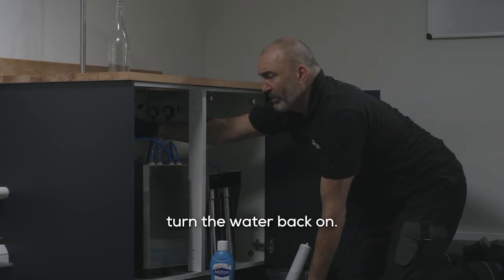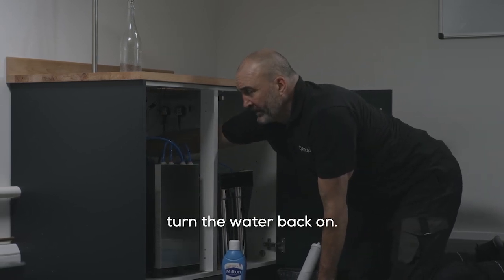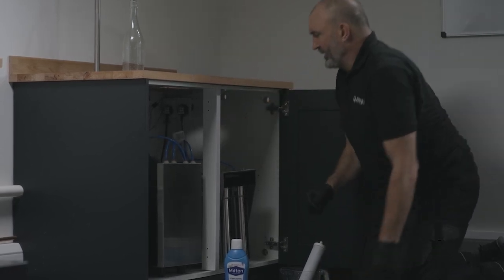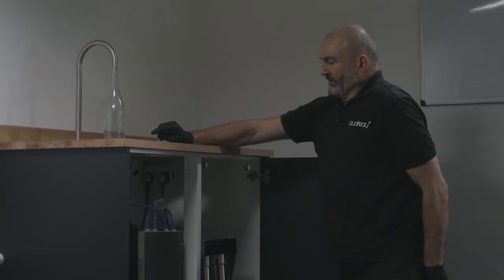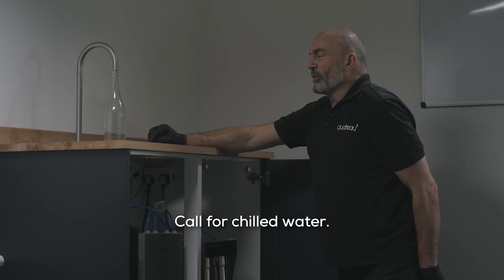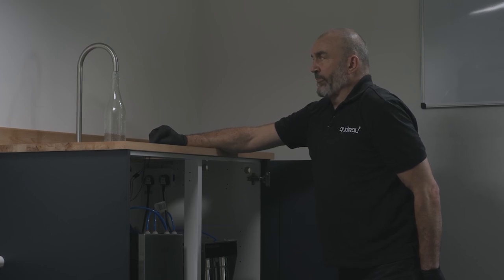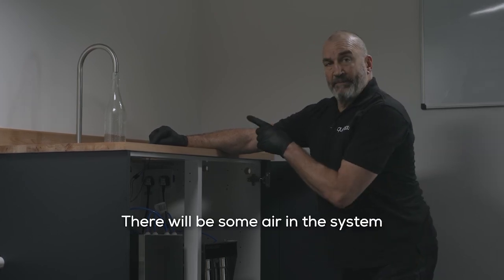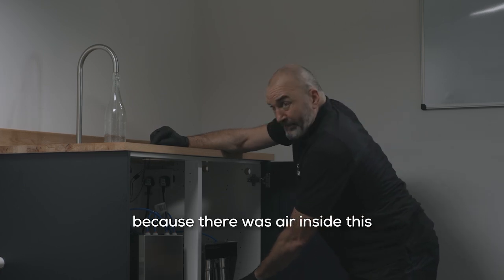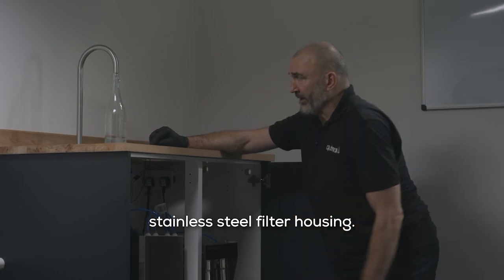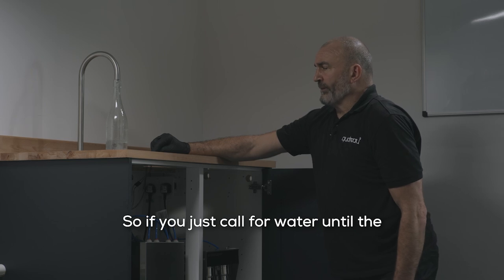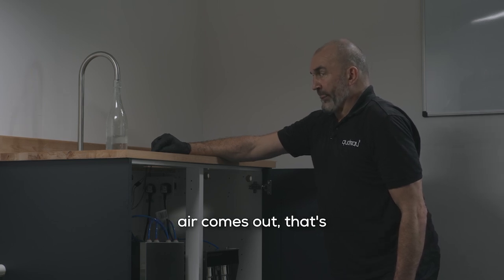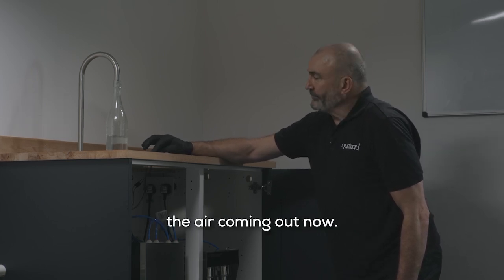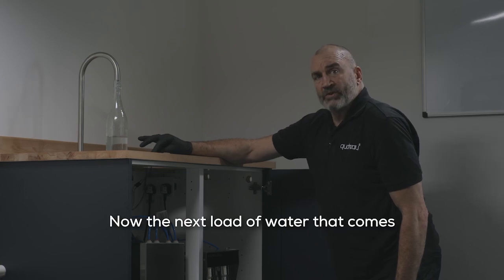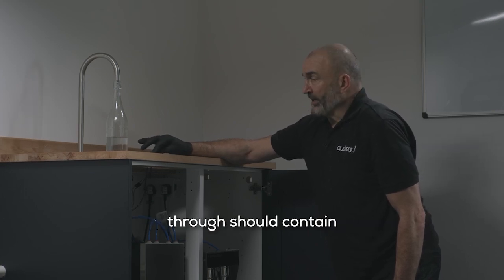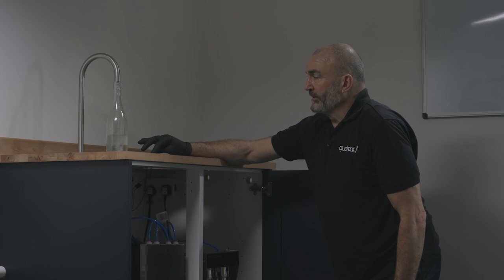What we need to do is turn the water back on. Call for chilled water. There will be some air in the system because there was air inside this stainless steel filter housing. So if you just call for water until the air comes out, that's the air coming out now. Now the next lot of water that comes through should contain the sterilisation fluid.